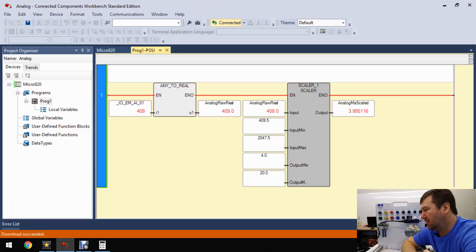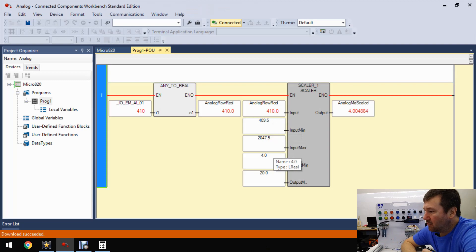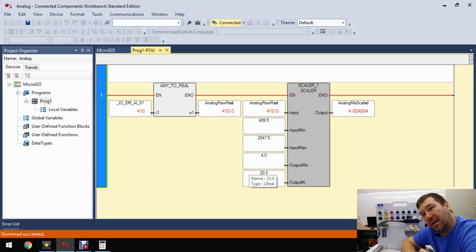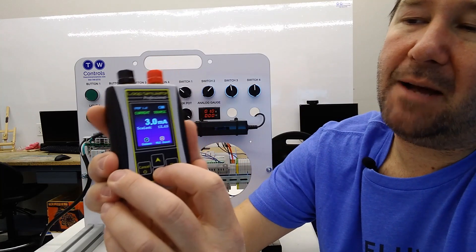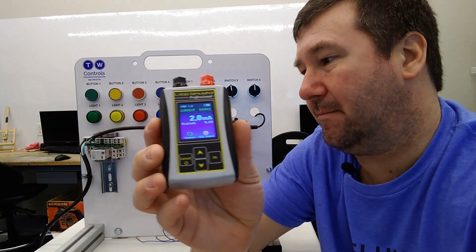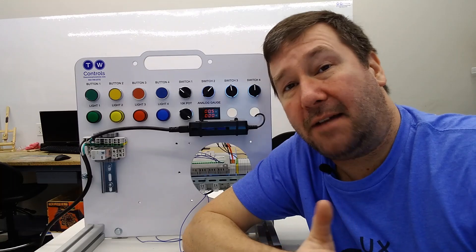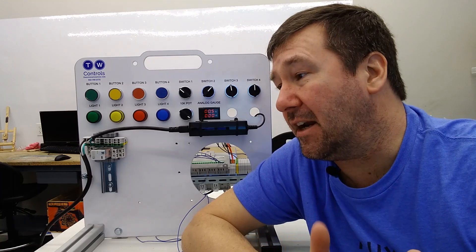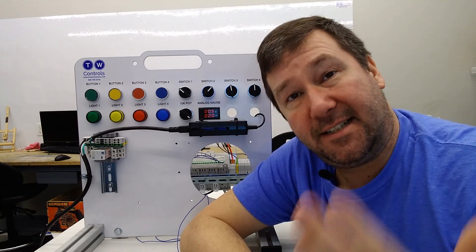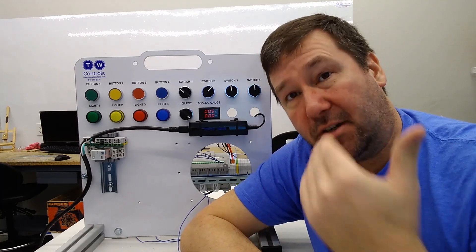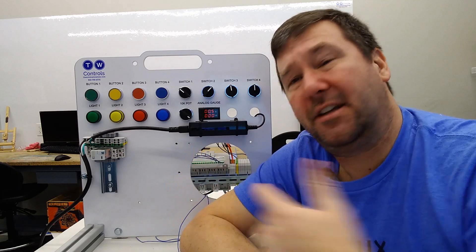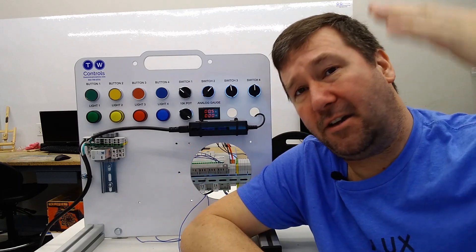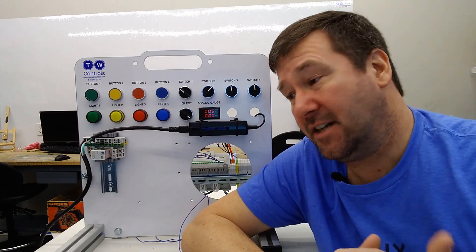But we were left with a small dilemma at the end - our scale is 4 to 20 milliamp, but if we drop down to 2 milliamp, then our scaled value will go down below. Sometimes that's fine, but in many cases it's not. Say this was going to an actual analog output, then you wouldn't want the value going beyond the scaled range.